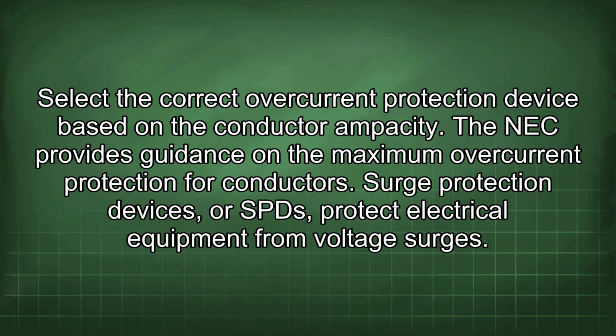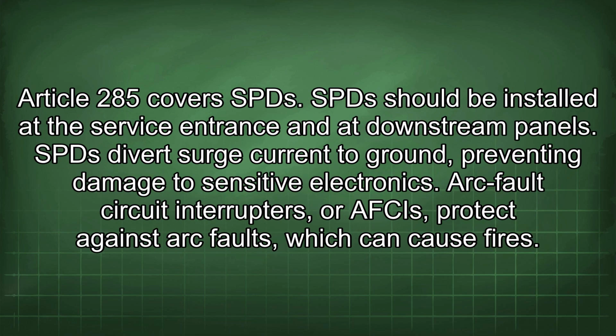Surge protection devices, or SPDs, protect electrical equipment from voltage surges. Article 285 covers SPDs. SPDs should be installed at the service entrance and at downstream panels. SPDs divert surge current to ground, preventing damage to sensitive electronics.